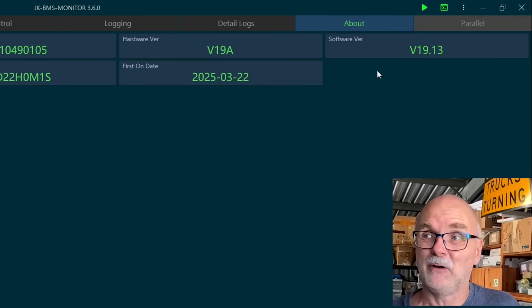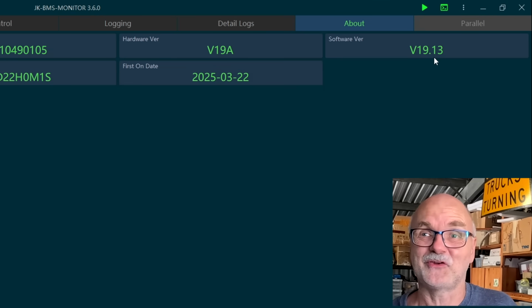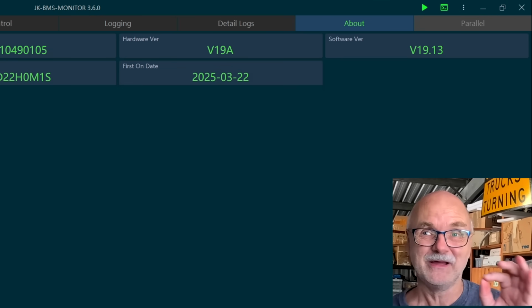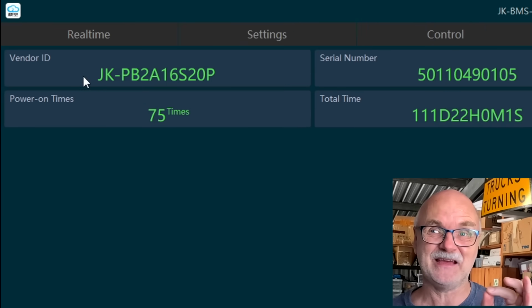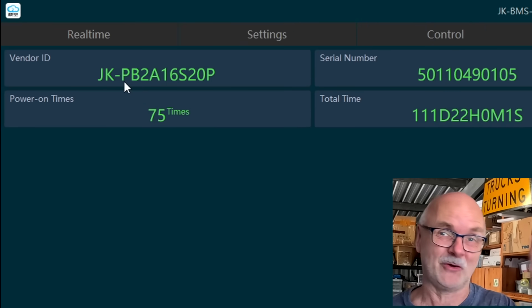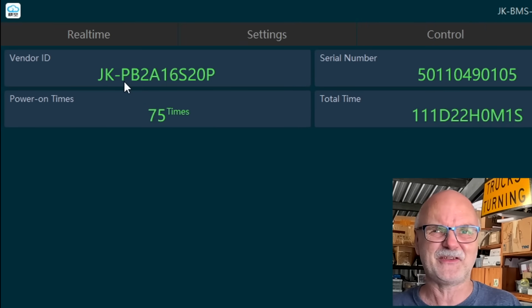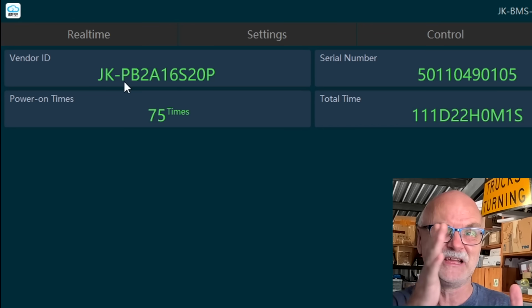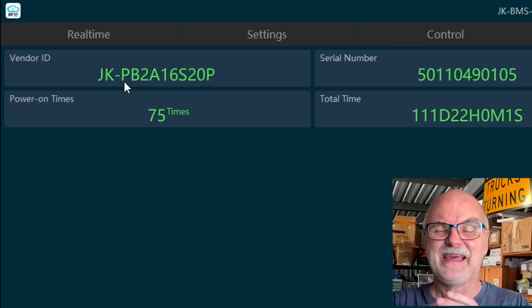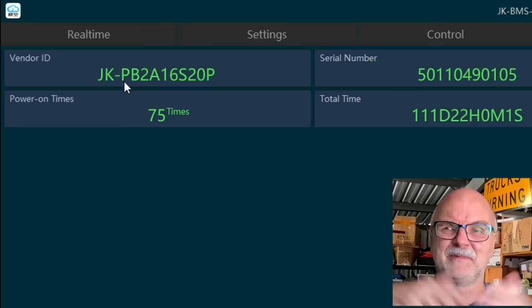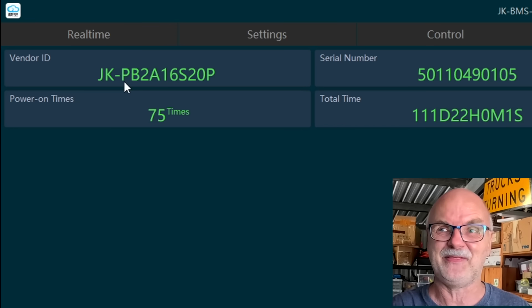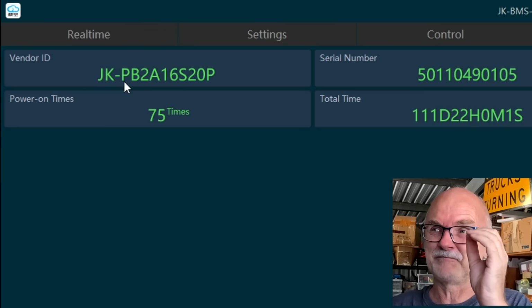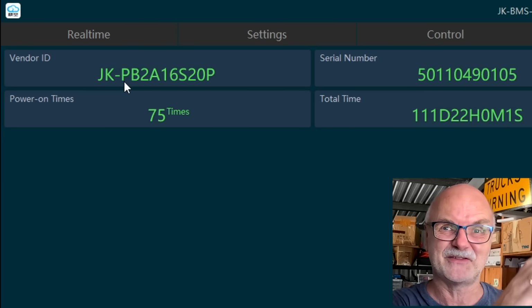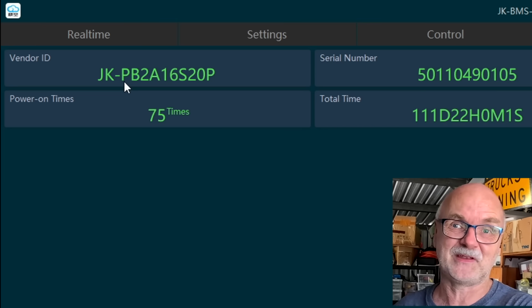We go under About and we're now on 19.13. You can see it has updated to the new vendor ID as well, JK-PB, not underscore anymore. Only up until version 19.10 it was JK underscore PB, then they changed it for whatever reason to JK dash PB, and that's why the software doesn't recognize the new firmware for your existing BMS.